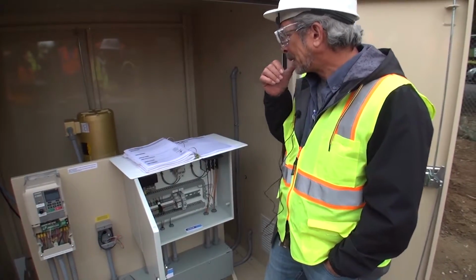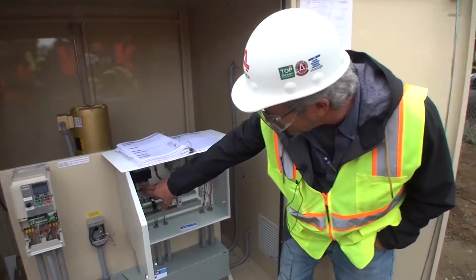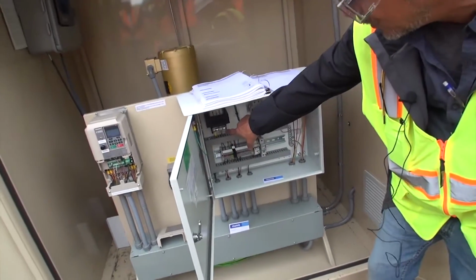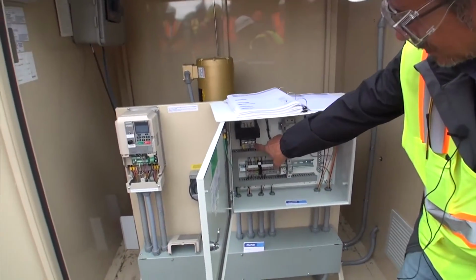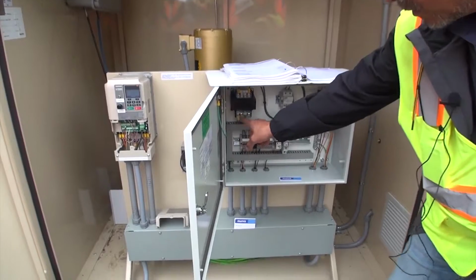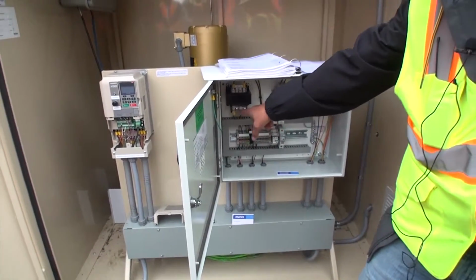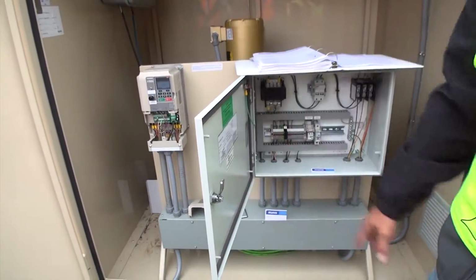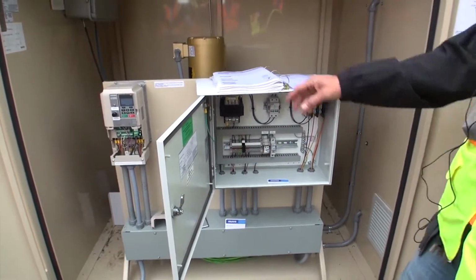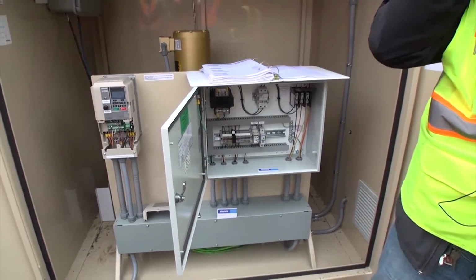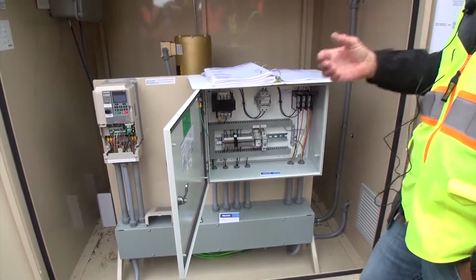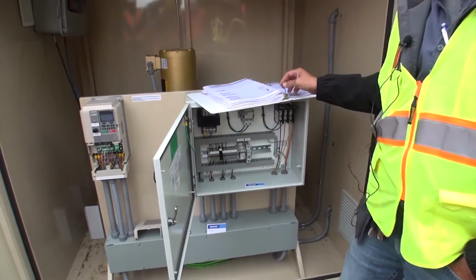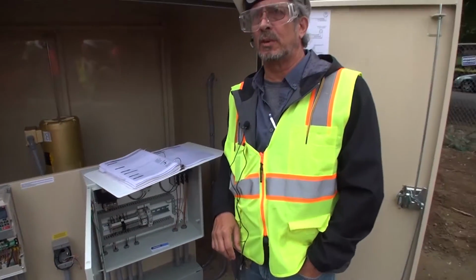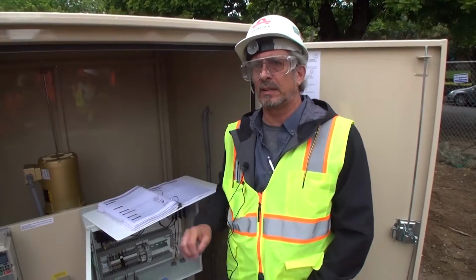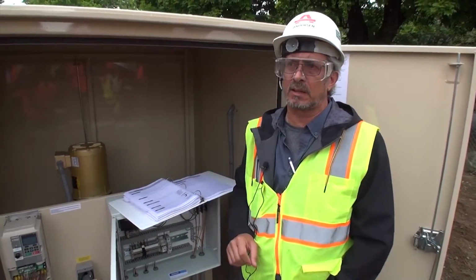The control voltage is your transformer here. You're going to measure across this fuse right through that little hole with your meter, and you can go to ground, or if you can reach it, you can go inside there and get the ground in there, or you can just touch it right here. And there's also control voltage in the drive, which is 24 volts DC. That is actually not that critical for you either, because everything is pretty much self-contained in the drive, and the drive, if it has a problem, is going to let you know.